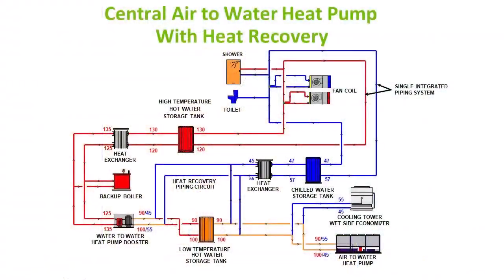Okay. So what are we going to do when it gets cold and it shuts off? That's not good, right? So we got a backup boiler over here on the left because that heat pump's not going to give you anything when it gets below 0. The other thing that happens with an air, or actually with any heat pump, is the lift from the temperature of the source or sink to what it is we're trying to heat. That lift with conventional refrigerants is about 100 degrees. So if it's 10 degrees outside, we're only getting 110 degrees off that air-to-water heat pump. That's not enough to heat the building. So we've got a little booster in here, this booster heat pump, so it pumps the heat from a low temperature up to a high temperature, and we can heat the building.